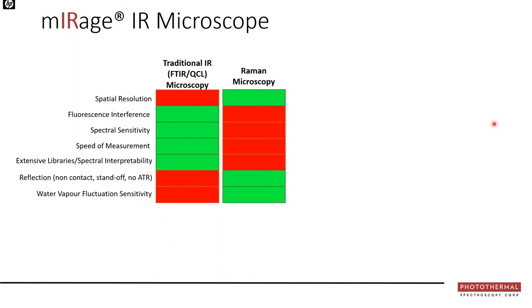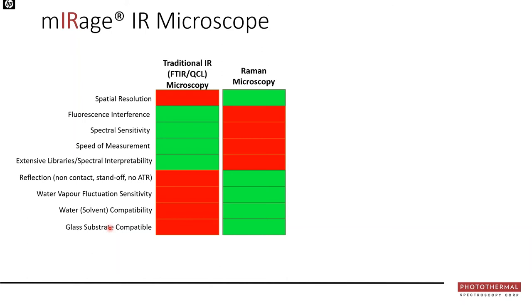For practical non-contact reflection mode, Raman wins — it's point-and-shoot with no sample prep. Water vapor fluctuations are a huge issue for IR but a non-starter for Raman. For water solvent compatibility, critical for life science, Raman is perfectly fine while IR is impractical due to required path lengths. Glass substrate compatibility also favors Raman, as glass is mostly opaque in IR. Spatial resolution in IR varies with wavelength while Raman is constant.